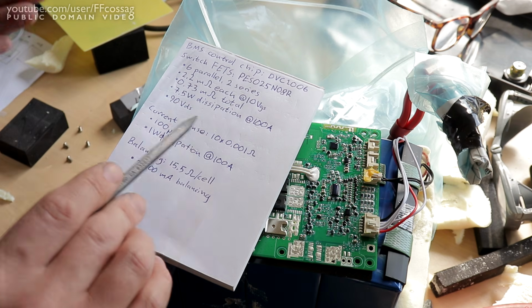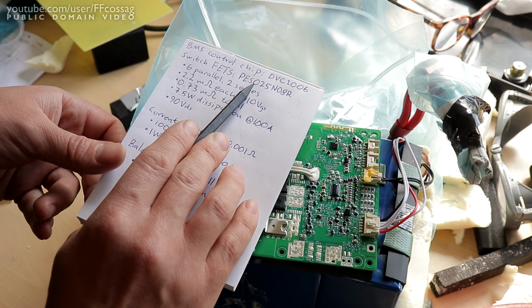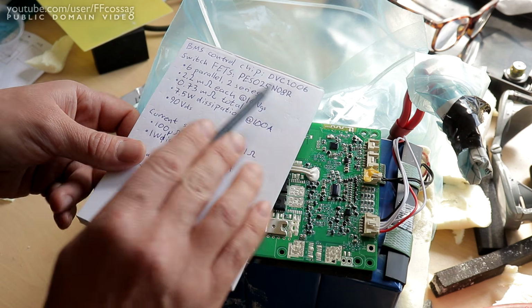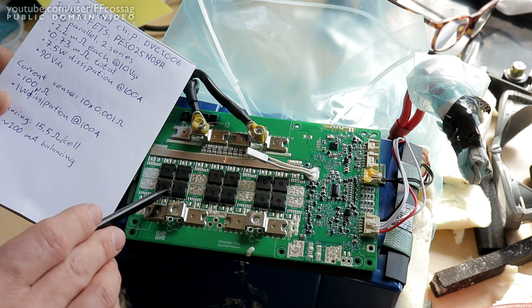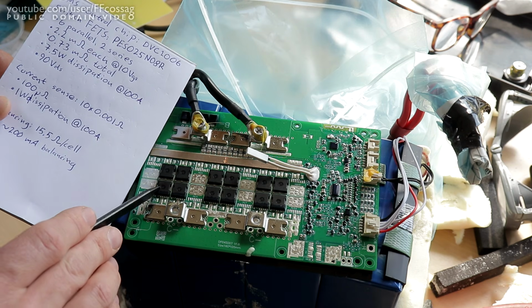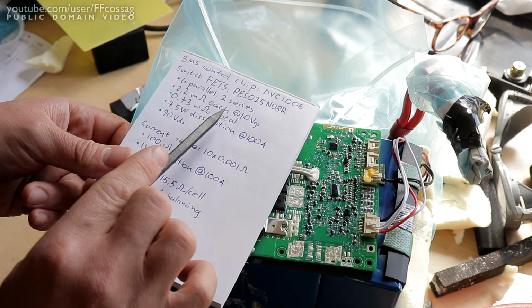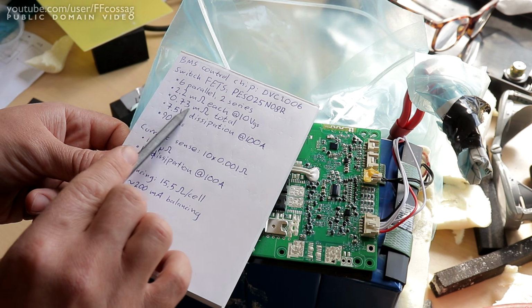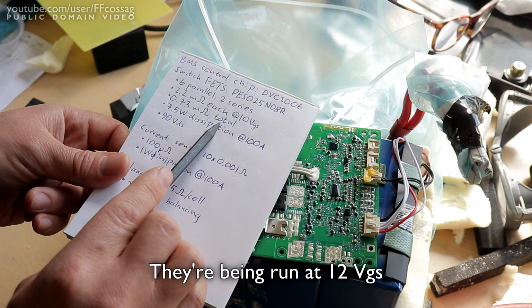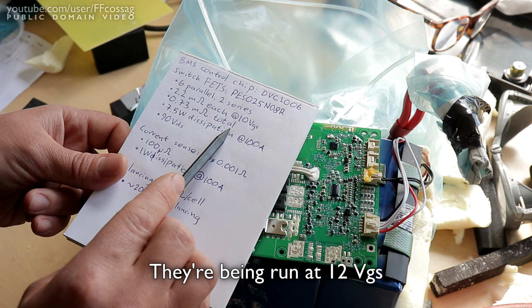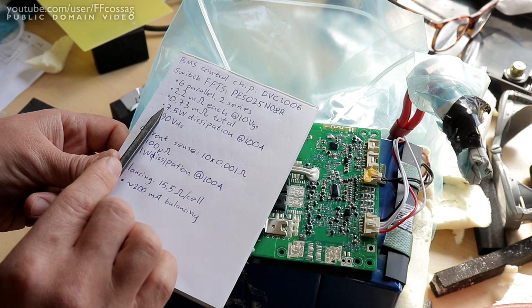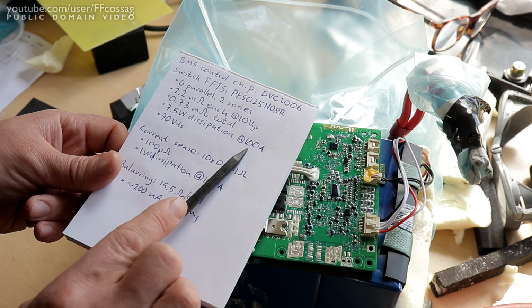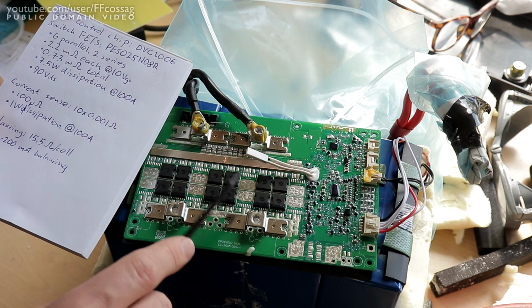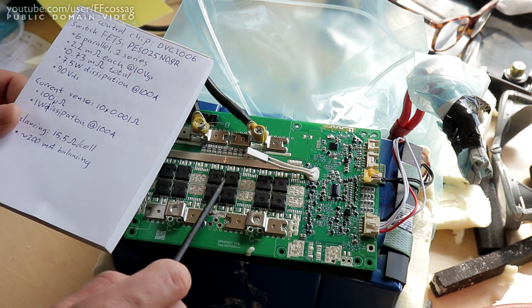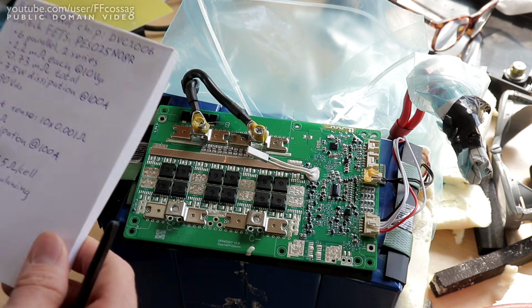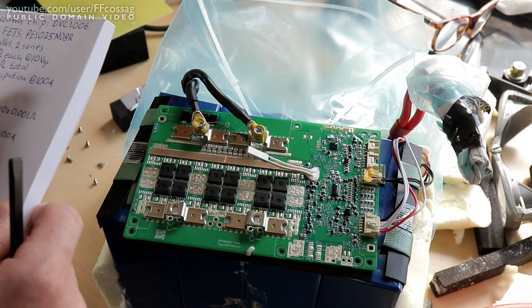So that's really good. The switch FETs, they are PE5025N08Rs. There are 6 in parallel and 2 in series, as there has to be. They're rated 2.2 milliohms each, which gives us a 0.73 milliohm total on resistance for this BMS while it's operating. That gives us a 7.5 watt dissipation at 100 amps, which is fairly high. This is at 100 amps continuous. This is going to produce quite a bit of heat. So 100 amps continuous is probably not what you want to do.